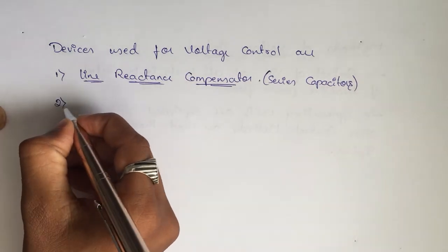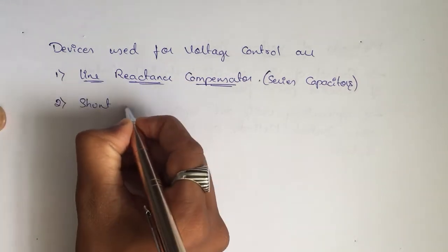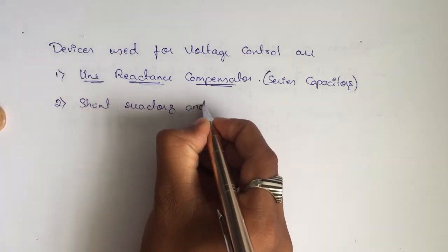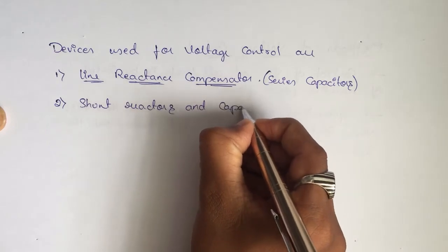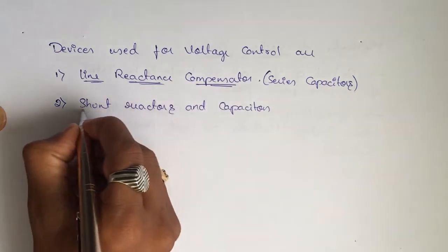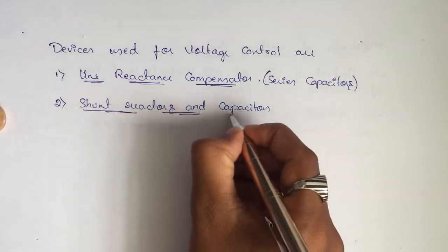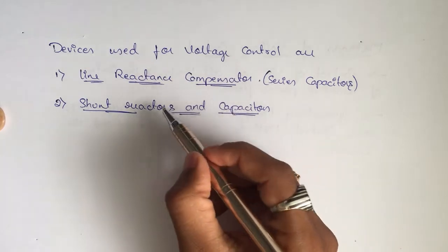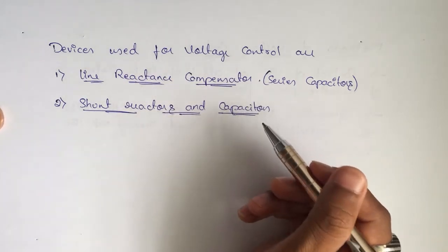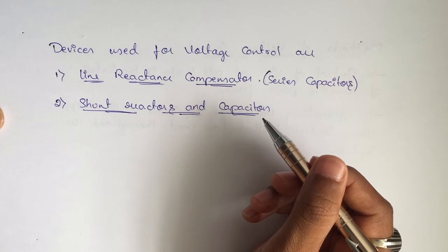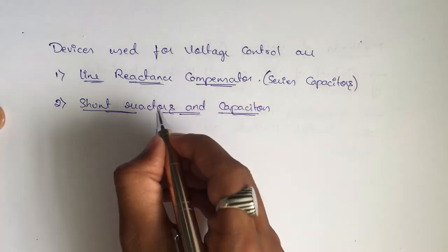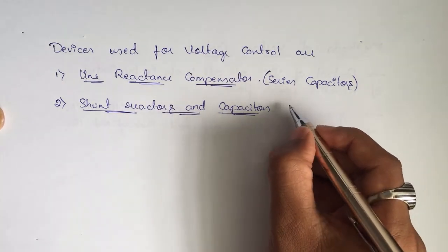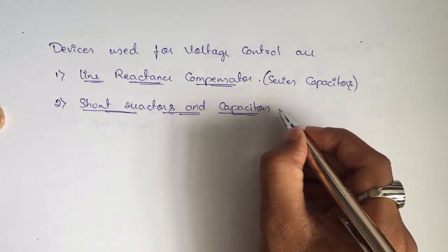Second one is shunt reactors and capacitors. Shunt reactors for leading power factors, and shunt capacitors for lagging power factors, which act as sinks and sources. Remember, reactors act as sinks and capacitors act as sources for reactive power respectively.